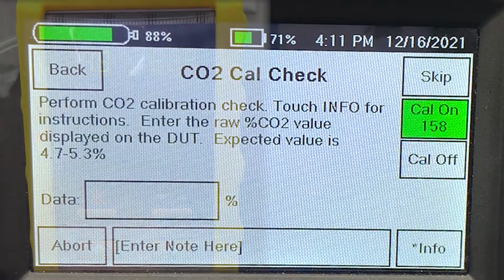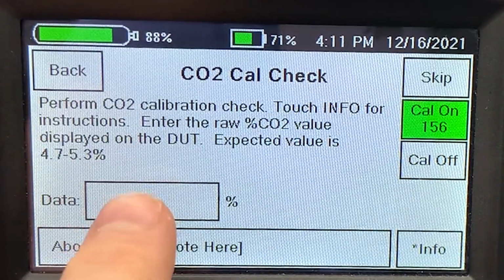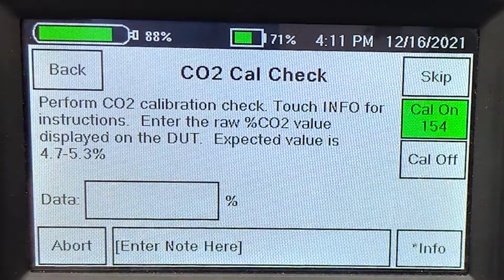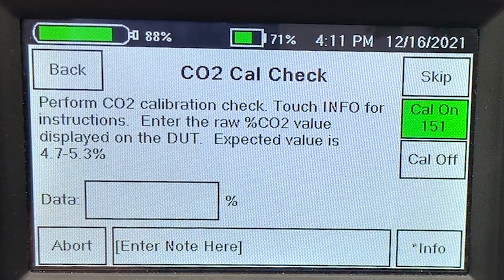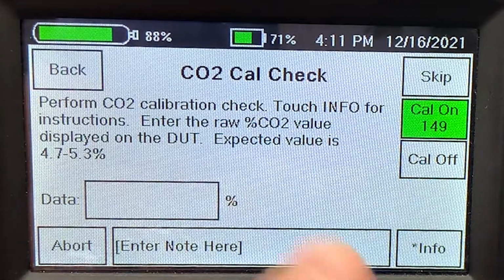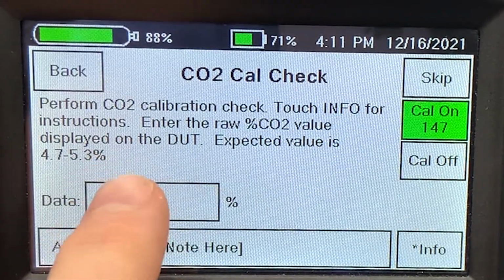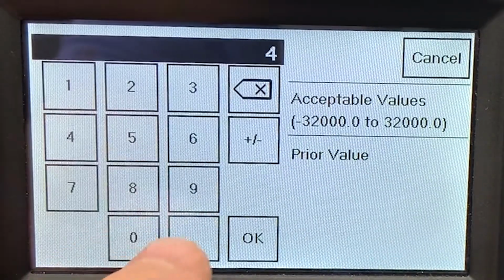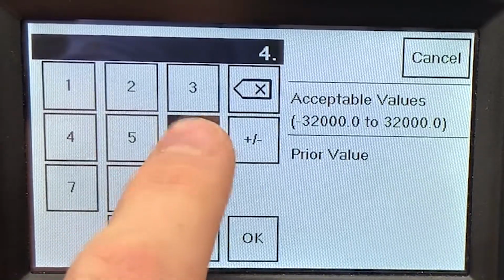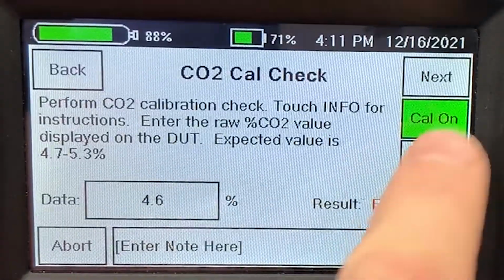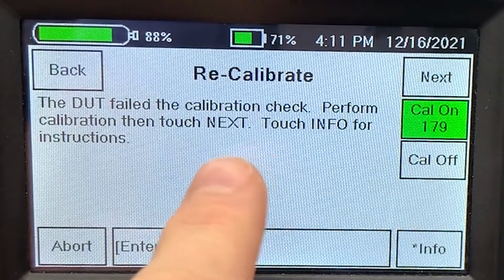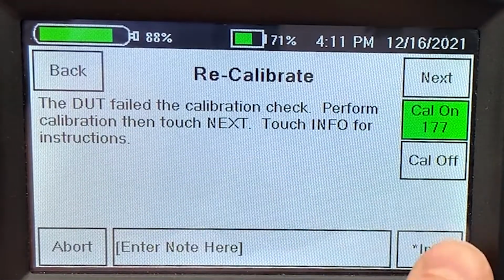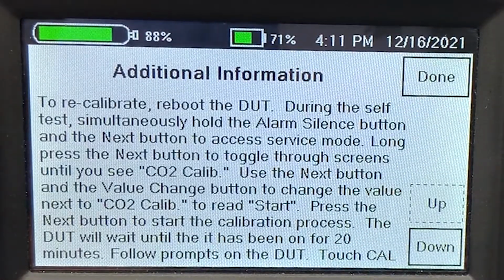So it's 4.9. This cal gas is 5%, which is very close, so it's within calibration. And we can enter that value here. If I do that and hit next, then this will go on to the next step. But because I want to show what happens if you enter a value that's failing, I'm going to enter a failing value here. And then I hit next. It's going to tell us now to recalibrate the monitor. If we touch info, it'll teach us how to do that.